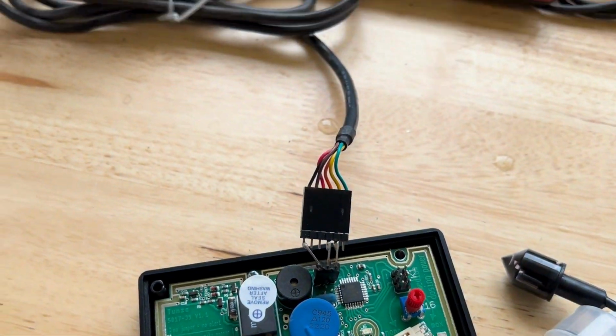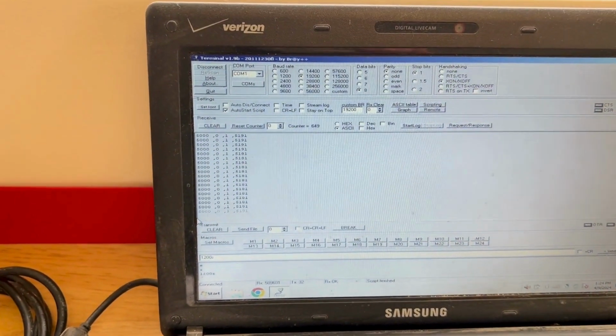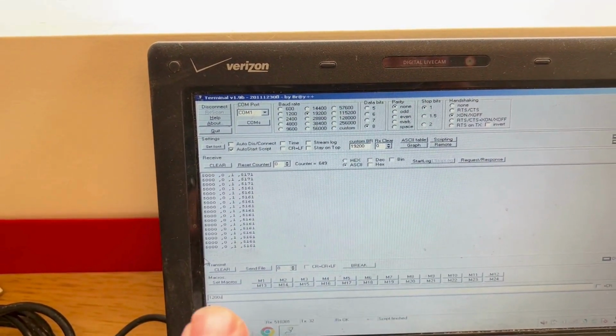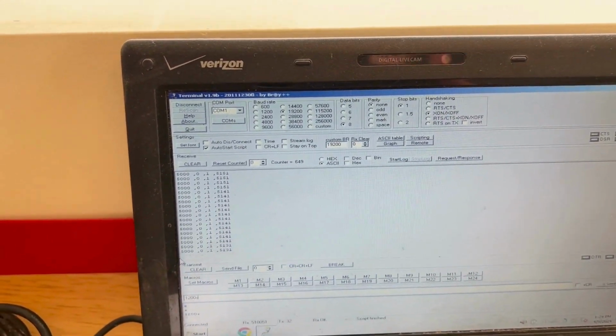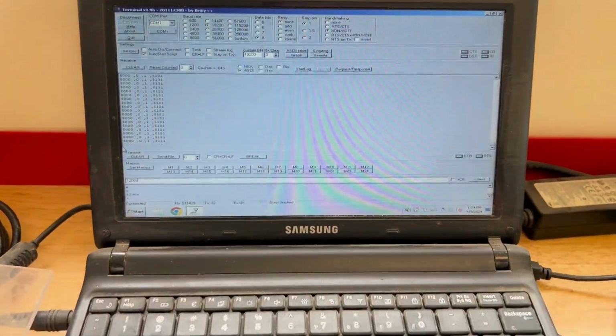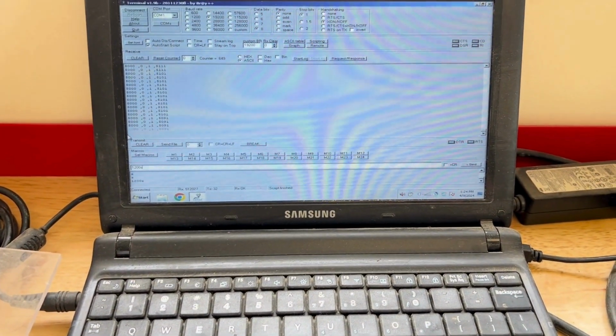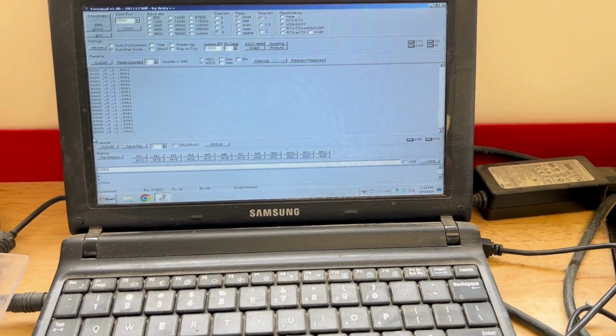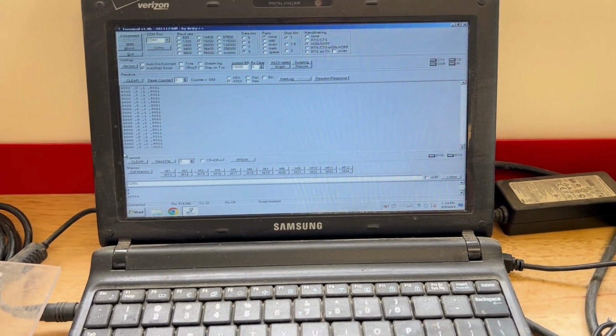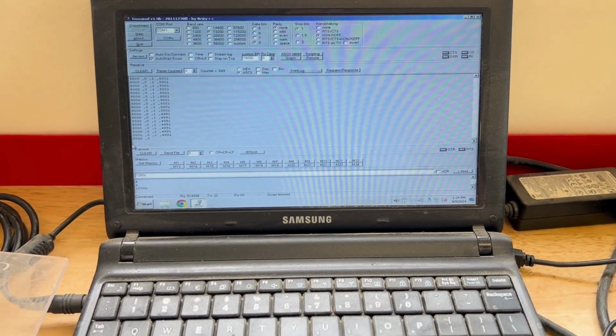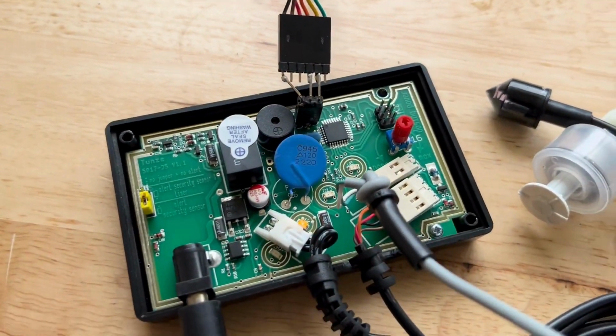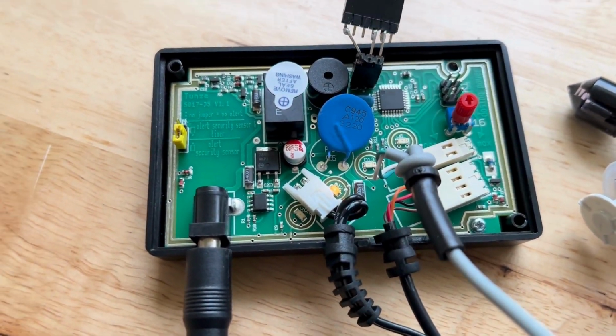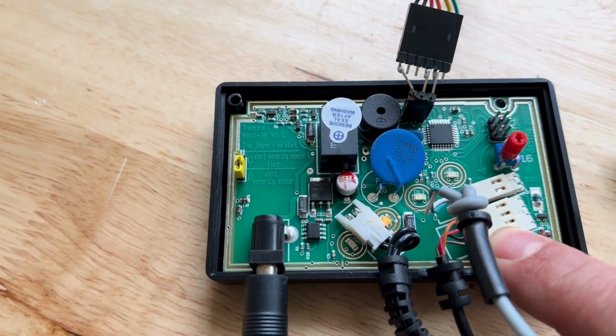The other thing that comes into play is our calibration settings. Here we have a readout of our sensor voltage, switch points, times. We can get in there and calibrate what point it switches at, and that'll also be very important because on older units all this was done manually. Every single unit came down the production line, they would get a reading of too high and too low, run a calibration. And while we're on that topic, when we get pre-2015, you won't have this plug.